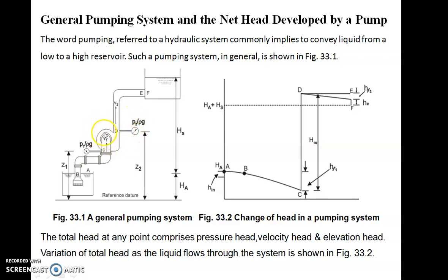So input is shaft power in case of centrifugal pump, impeller power is after shaft power, and after impeller power there is the output power, that is nothing but your manometric head. Rho g Q HM is the manometric power which is produced by the pump.